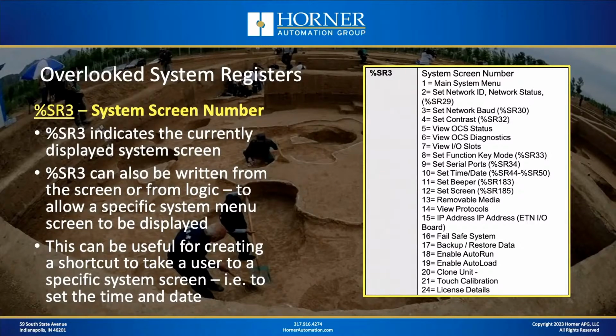But what's more useful is the ability for an application designer to write to SR3 to force a specific system menu screen to be displayed, to provide a shortcut for their users to go in and, let's say, change the time and date. So instead of creating a time and date screen on their own as a system designer, you just create logic that effectively writes to SR3 a value of 10, and then that sends them to the set time and date screen. So that can be pretty useful. Some of these other system menu screens can also be useful, but by far, the most useful one is for setting the time and date. So let's go ahead next and demonstrate that.